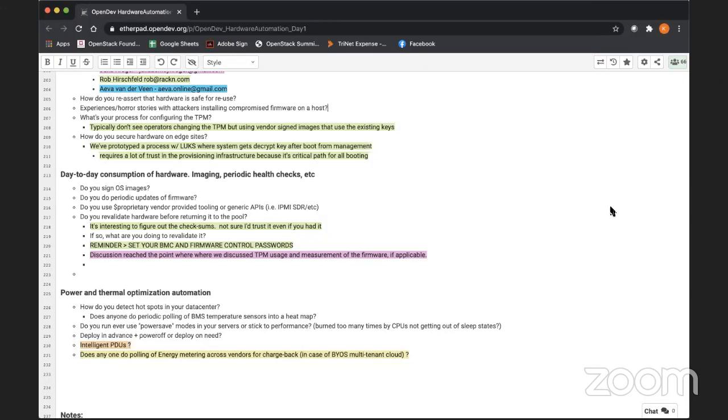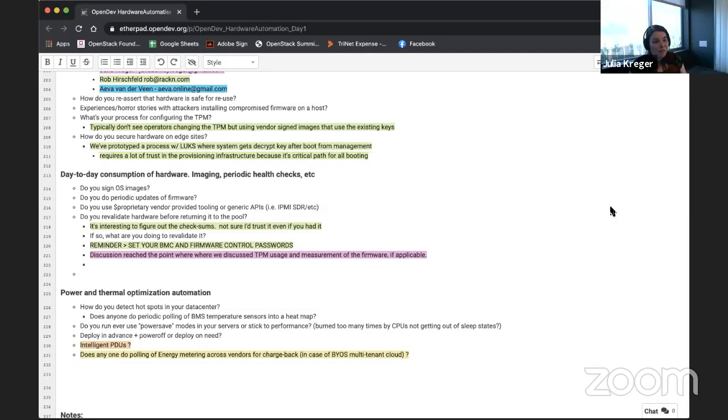We don't, but our power circuits are kind of pretty over provisioned, and luckily we have a lot of power in. It's all hydroelectric here. So usually power is pretty easy to come by on our side here. So I think what James's point is kind of driving the discussion towards is when you have a transformer and you're loading one side of the transformer, you actually lose a lot of efficiency because you've lopsided the load on it.